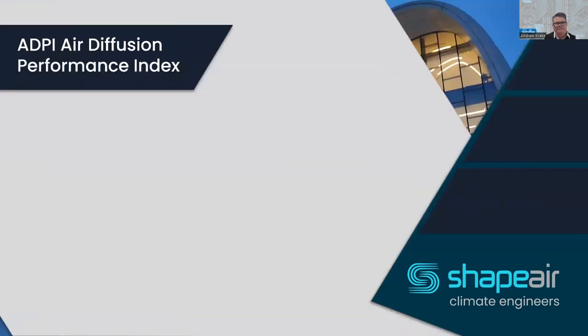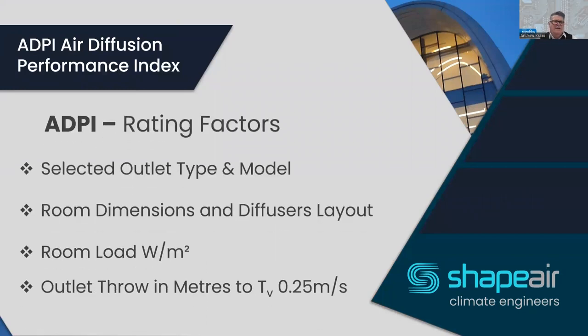The ADPI is a rating value. The factors used are: the type of outlet and model, the room dimensions and layout of the air diffusion equipment, the room load as it varies, and the throw of the outlet to a terminal velocity of 0.25 m/s.